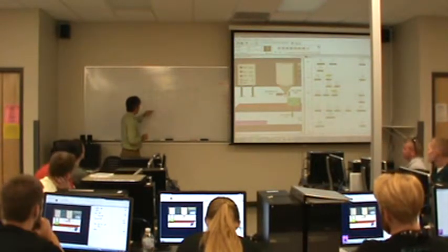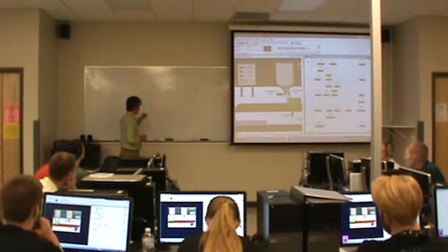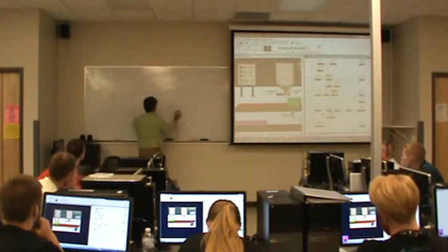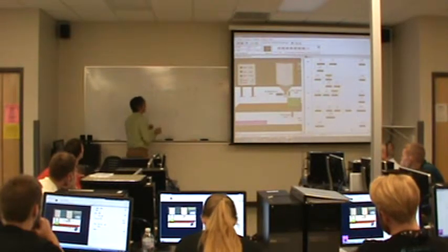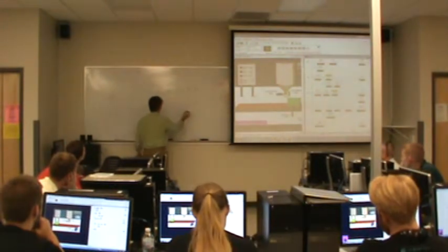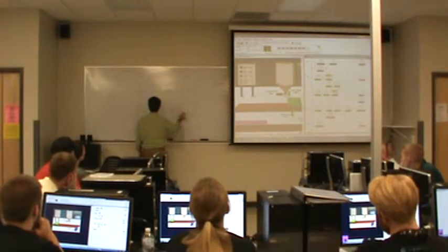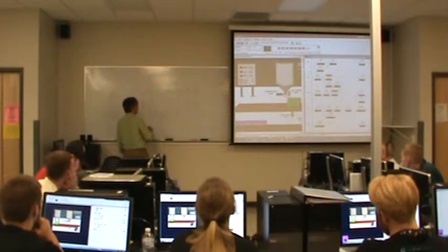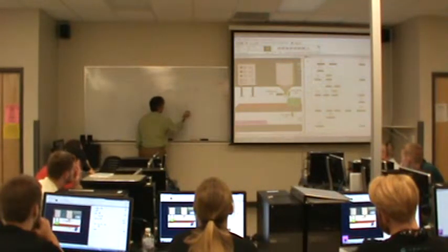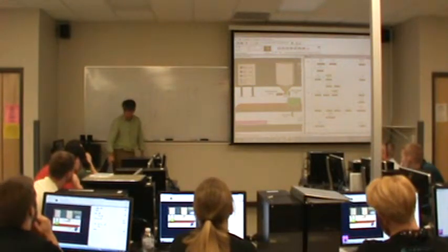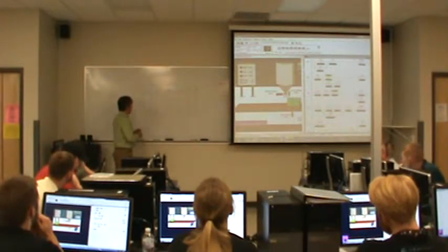Okay. How about level? Well, let's see. If level is not true, motor's on, valve is going to be off in both of these cases because we've got a moving box. We're not filling, and we would have a full box, so we should program that on, even though it's going to shut off next scan. Program it on here, fill's not true, so there we go. We only have 2 more lines to program.